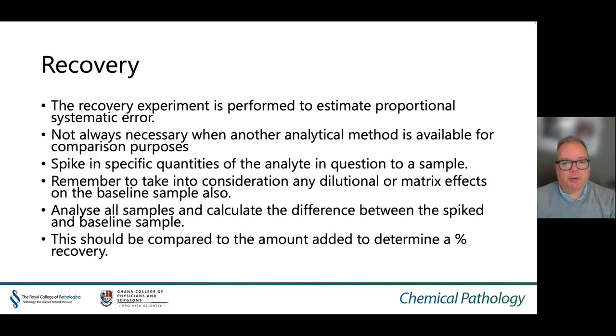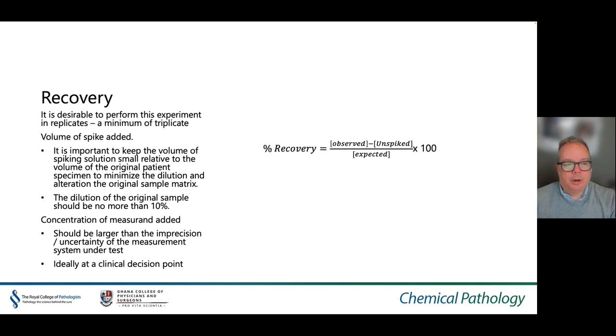A recovery experiment is performed to estimate the proportional systematic error. It is not always necessary when another analytical method is available for comparison purposes. You spike specific quantities of an analyte into the sample, remembering to take into consideration any dilutional or matrix effect on the baseline sample. Analyse all samples and calculate the difference between the spiked and baseline samples; the results should be compared to the amount added to determine the percentage recovery. It is desirable to perform this experiment in replicates — usually a minimum of triplicate analysis. When taking into account the volume of spike added, it is important to keep the volume of the spiking solution small relative to the volume of the original patient specimen, to minimise any matrix effect.